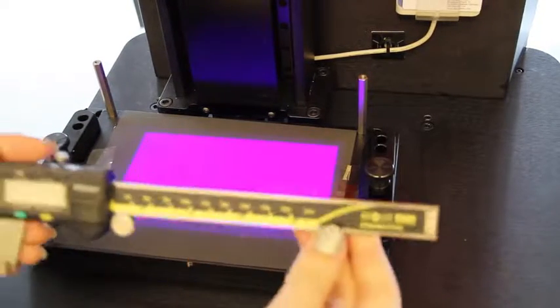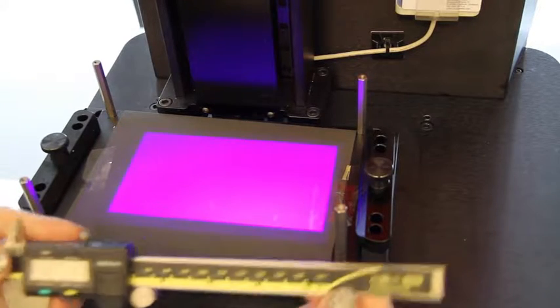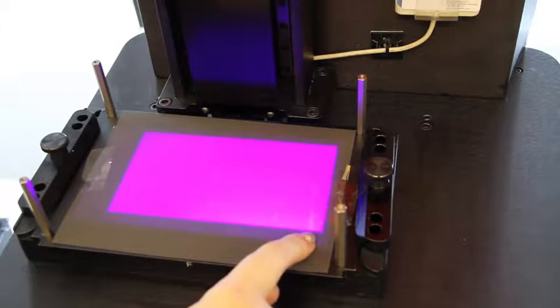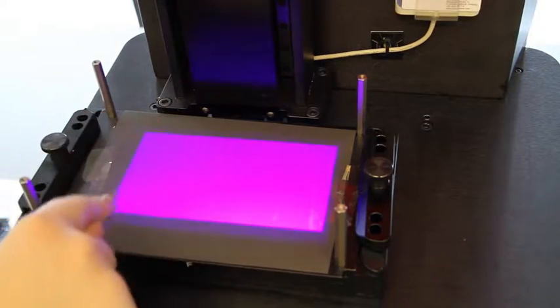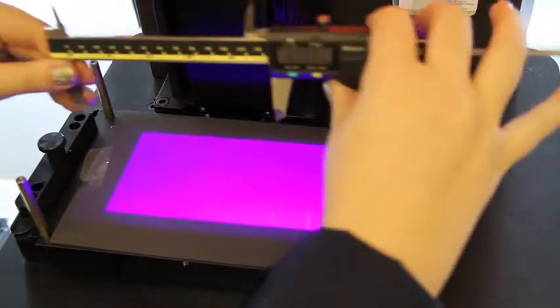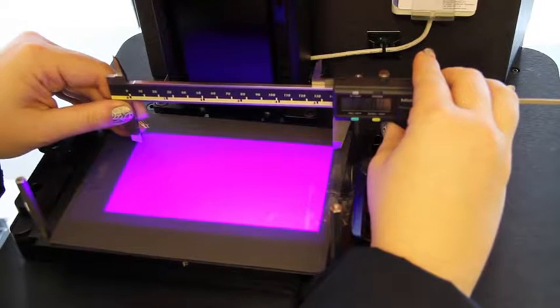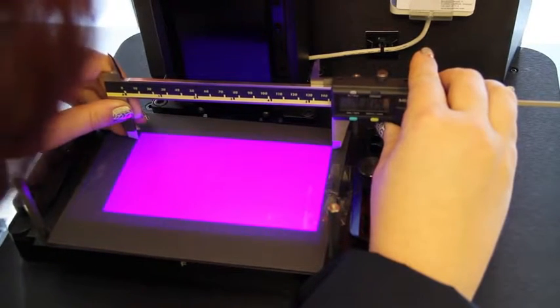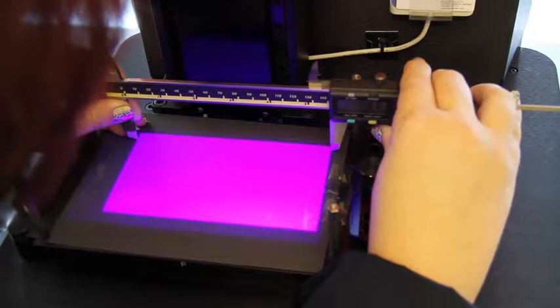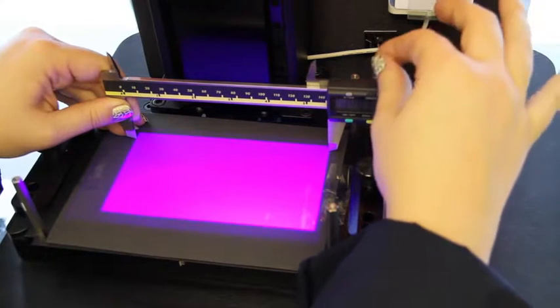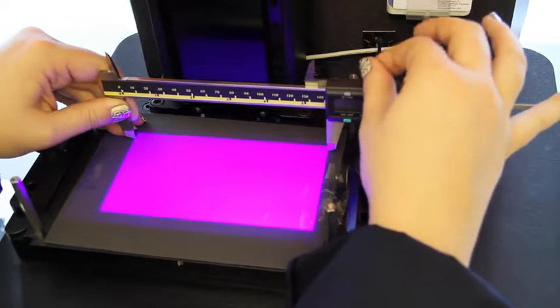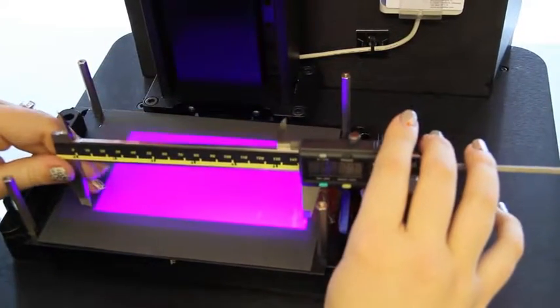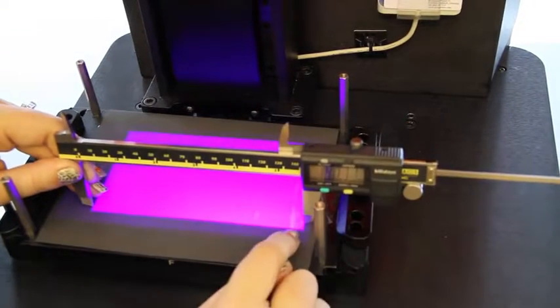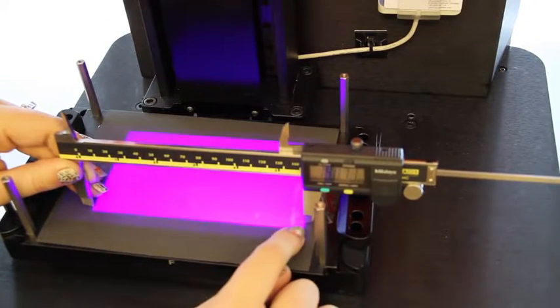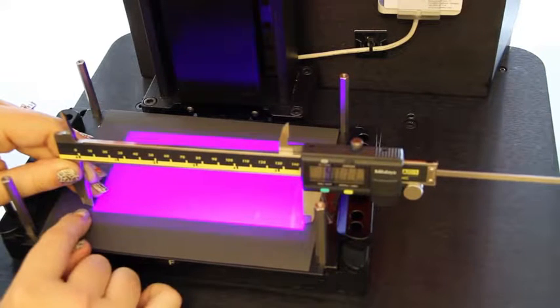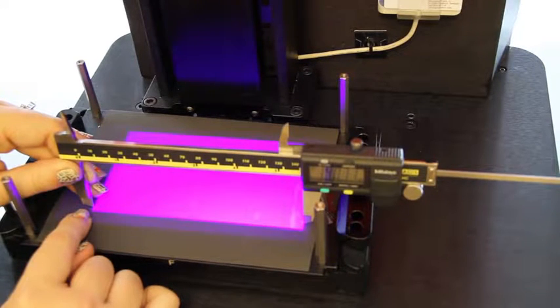The next tool I'm going to need are my digital calipers. These will allow me to measure and check the parallelism of both the X and the Y. I'm going to open up my calipers, set them on either side of the box of light, making sure they're straight across from one another. Once I line this up, I'm going to tighten my little screw, and I'm going to come down and measure the bottom side. They should line up roughly the same with the box of light. If for some reason they are larger or smaller, call technical support.